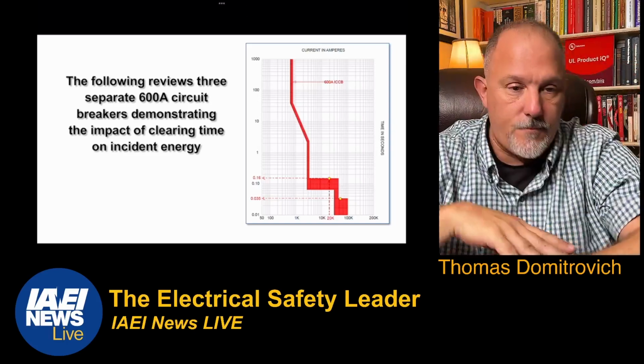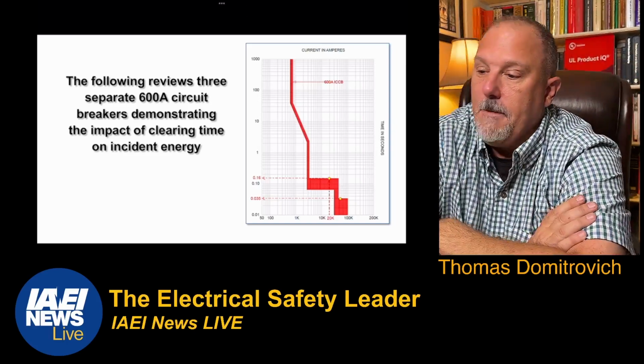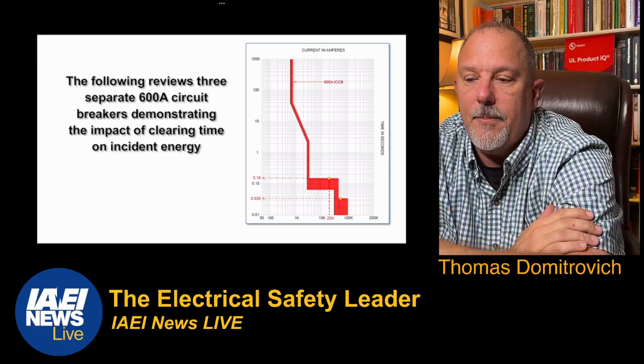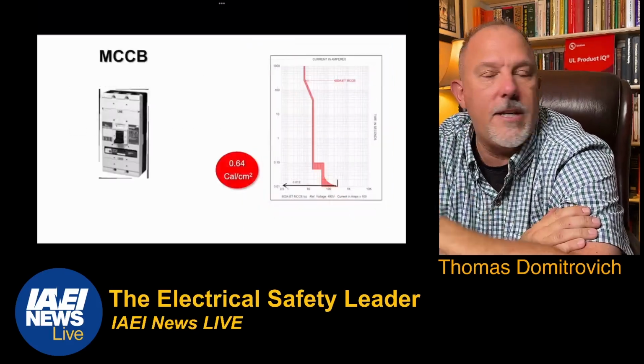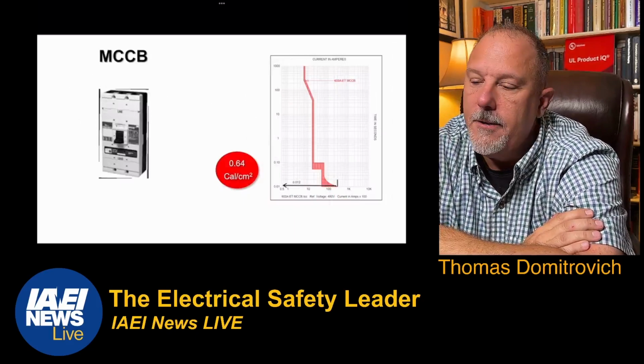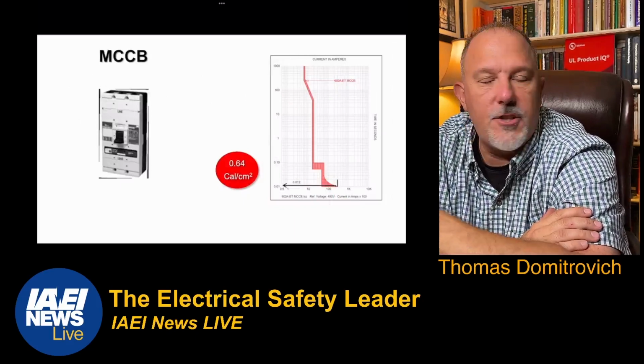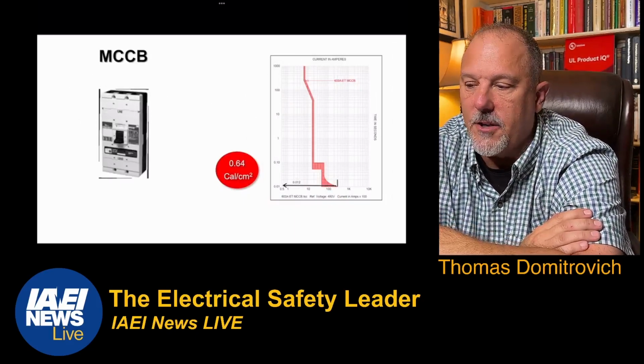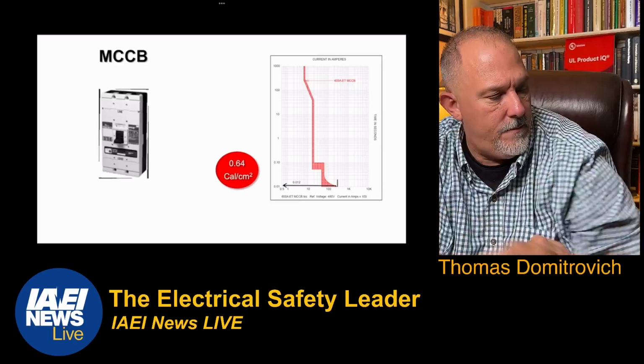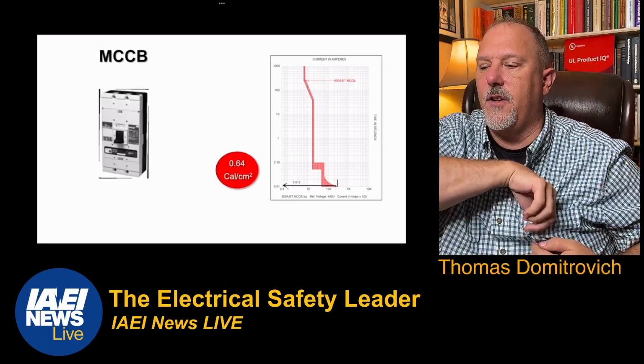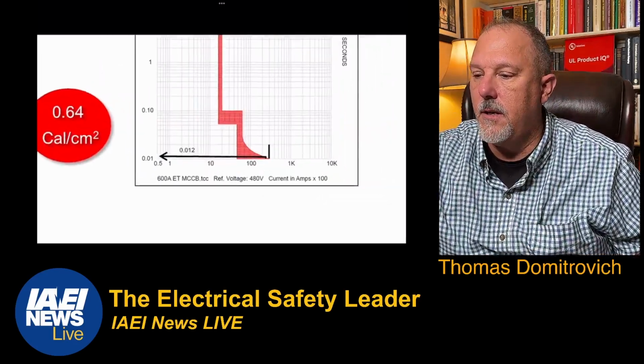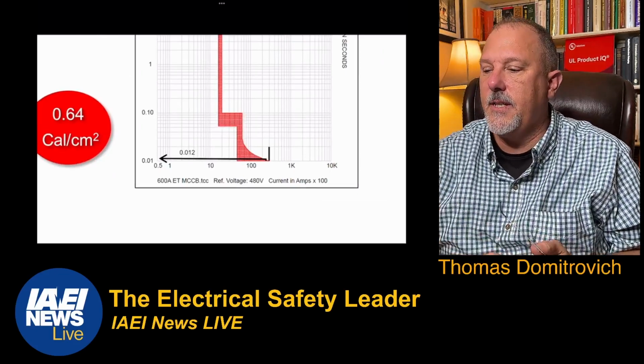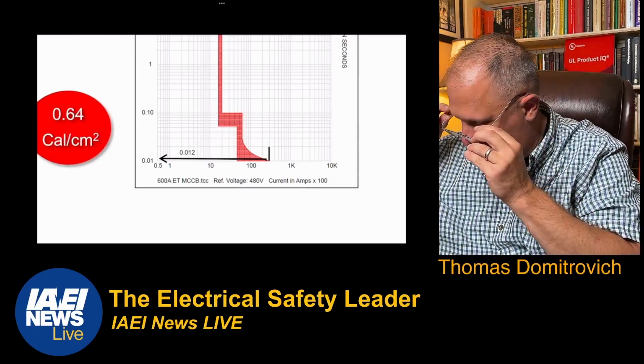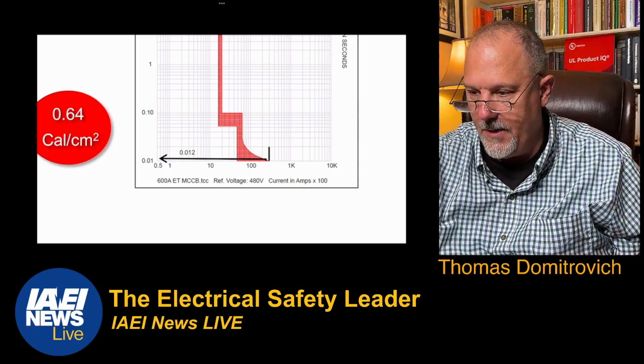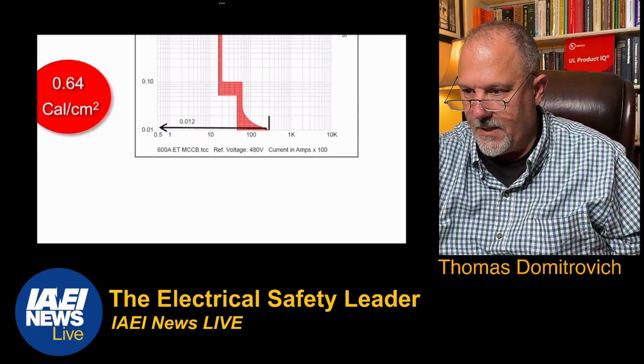Anyway, so here's what we're going to do here. We're going to take a 600 amp, 3 different breakers. A molded case circuit breaker is the first one. That's the trip curve for a 600 amp molded case circuit breaker, and I have the same fault current flowing through each of these, which is, if this is times 100, where's my pen?